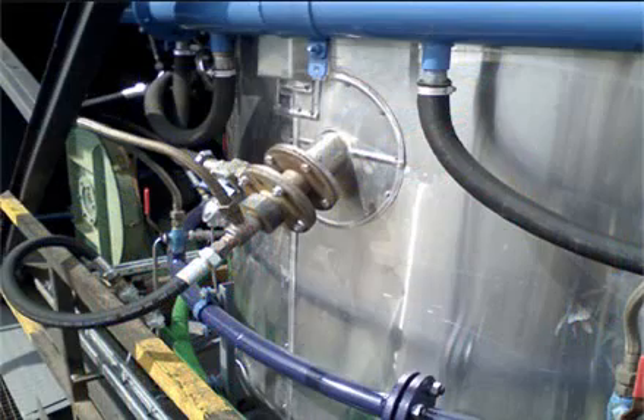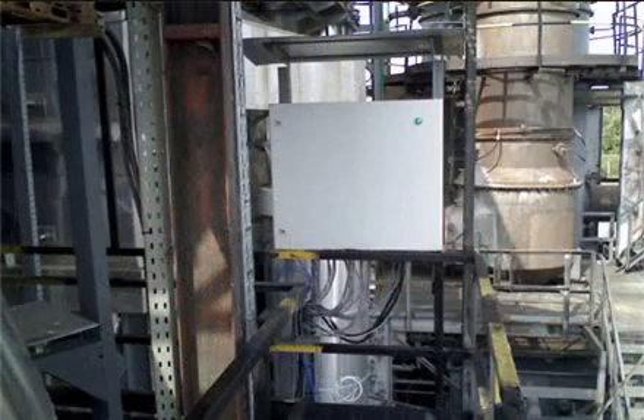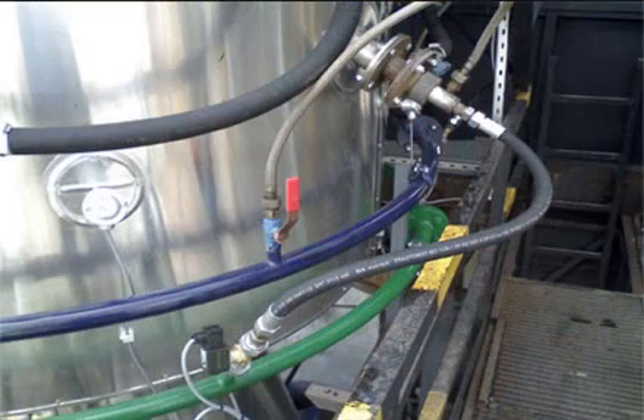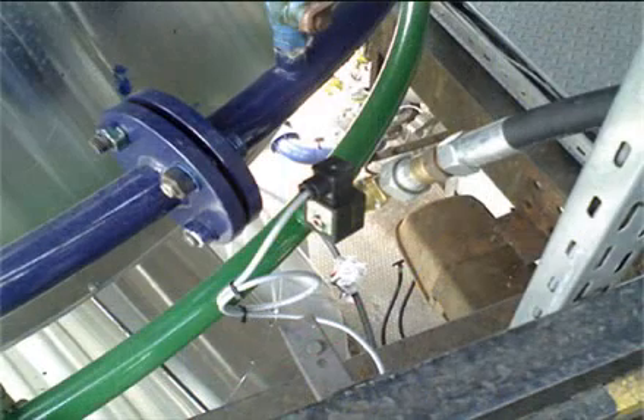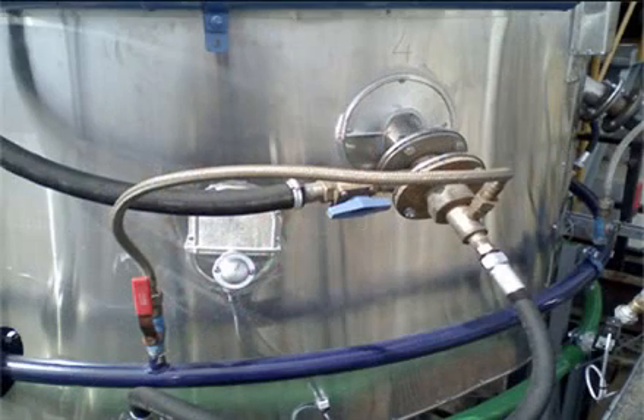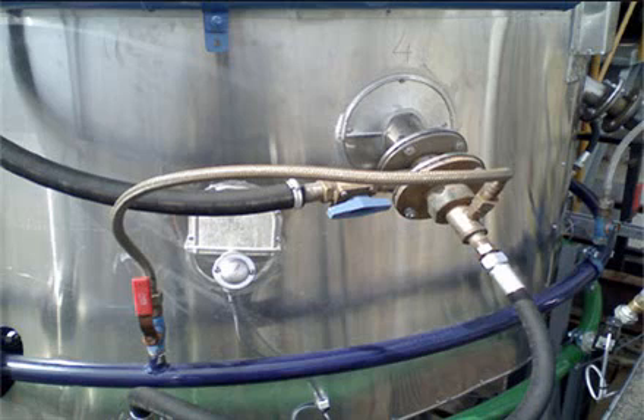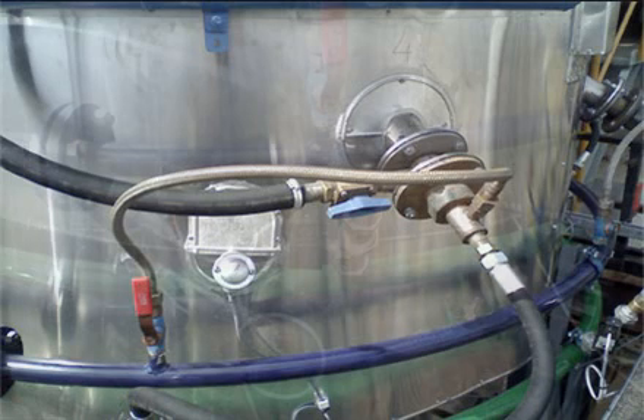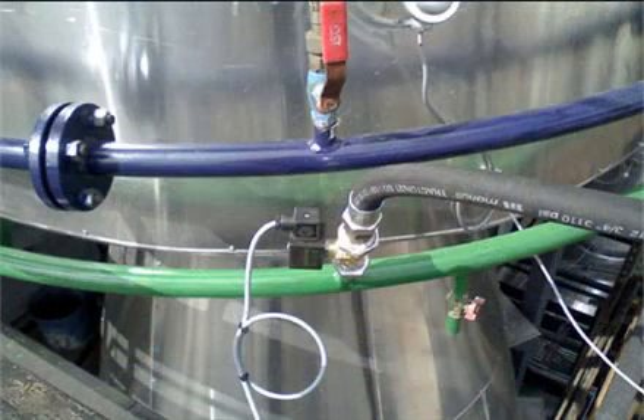At the end, a fine-tuned injector configuration was built into the redesigned cooling tower, but other improvements were also carried out. New control electronics was developed, and it measures the wall temperature of the tower in more than 30 points. The quantity of the water to be injected is set based on the temperature values near the injection points. This way, the system can quickly follow the fluctuations in burner heat load and can add just the necessary cooling water.